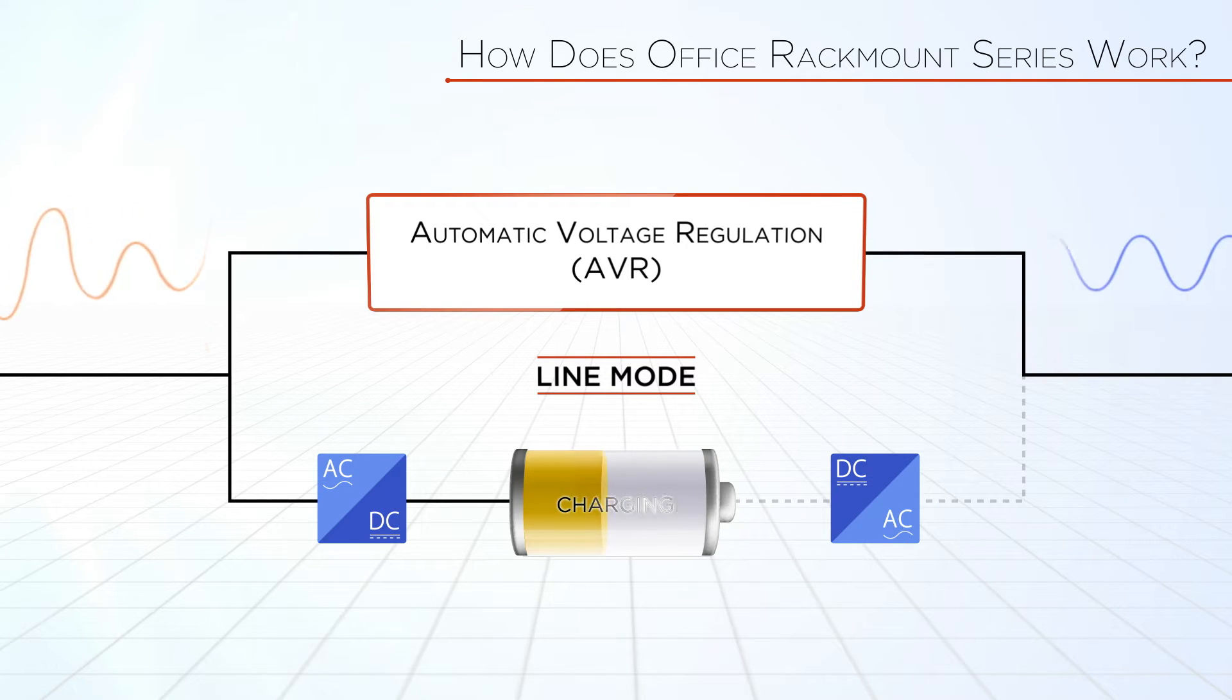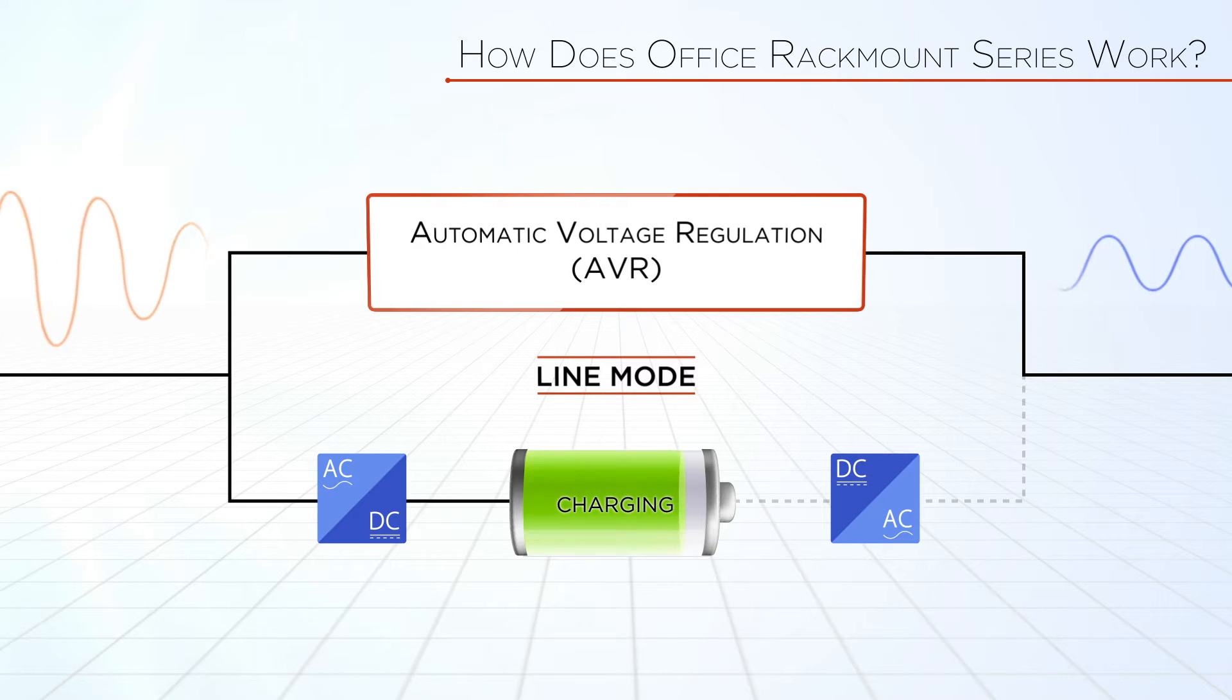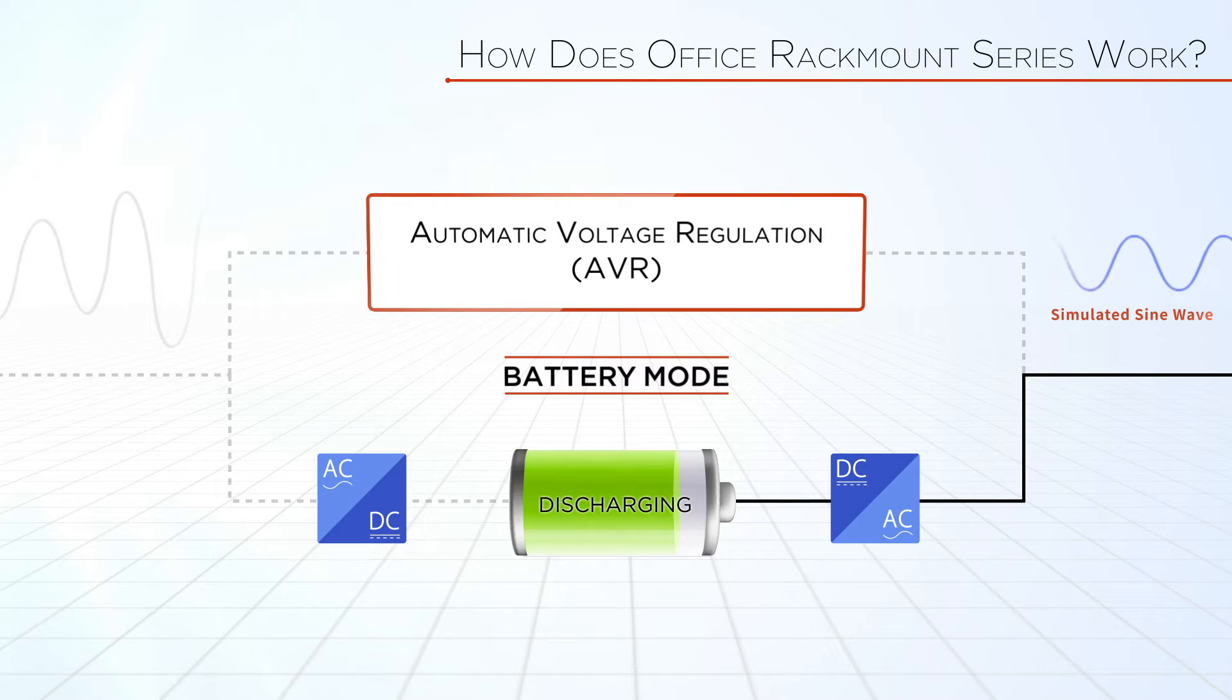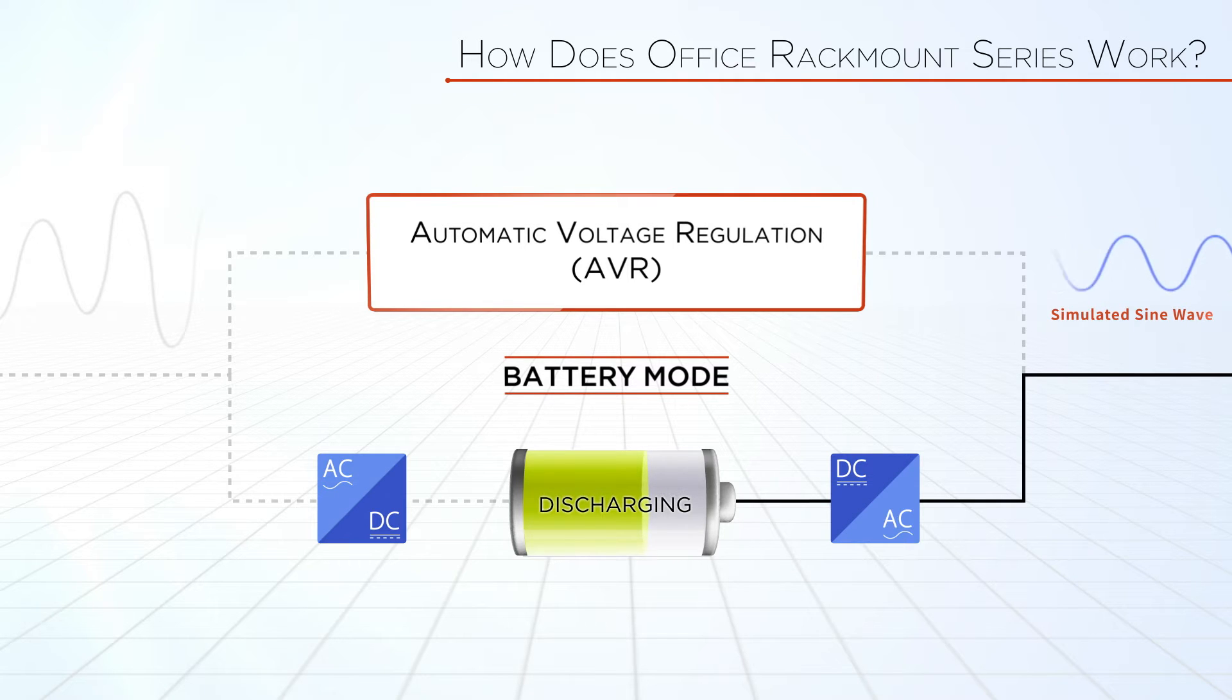The UPS normally operates in Line Mode in which power is stabilized via AVR while also recharging the built-in battery. When power quality exceeds normal power criteria, the UPS will automatically transfer to battery mode in order to provide continuous power for the connected loads.